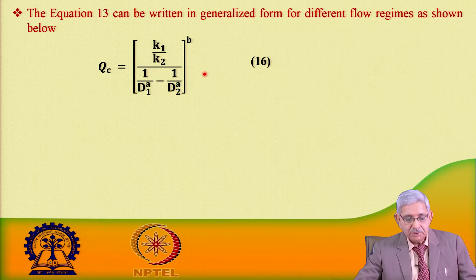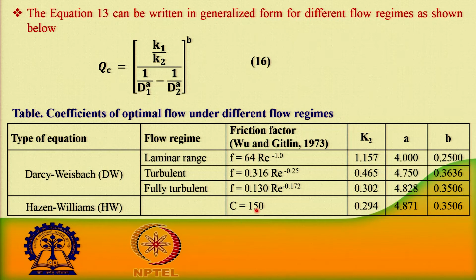So, equation 13 can be written in a generalized form, that is, your optimal flow rate Qc can be given by this expression, where two cases have been considered. This is a generalized form of the equation. The Darcy-Weisbach equation has a provision to estimate the friction factor f when the flow is laminar, transitional as well as turbulent, whereas the Hazen-Williams equation is used only for a specific case, where there is no provision to change the value of f. Normally, this is for the turbulent flow case.